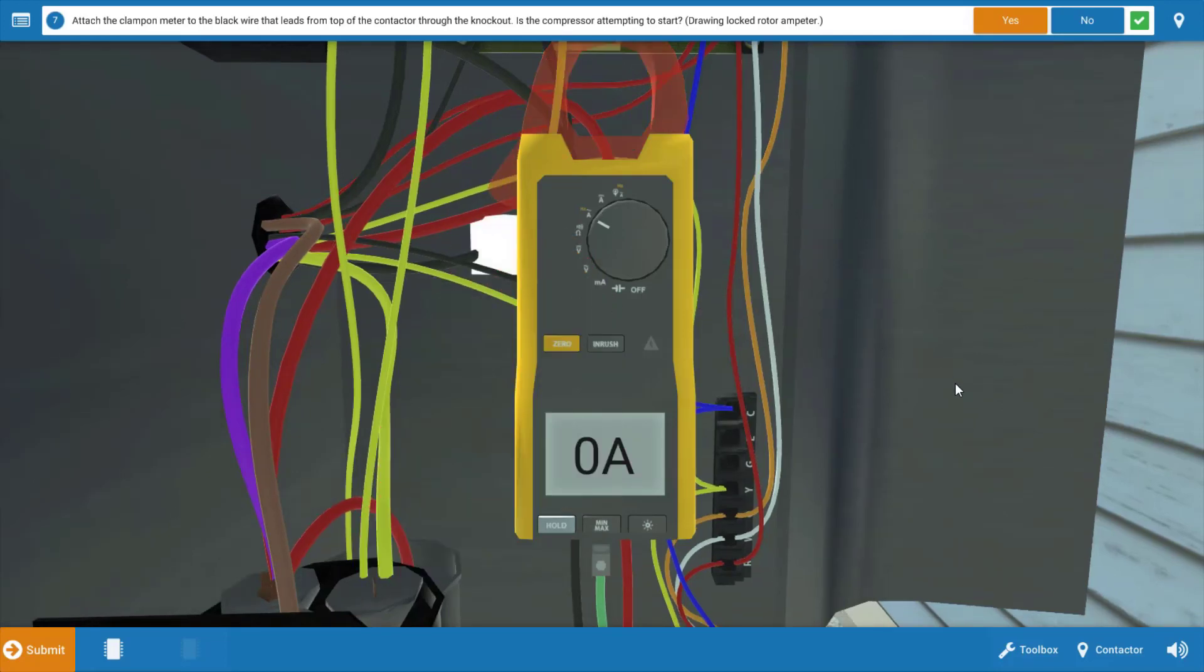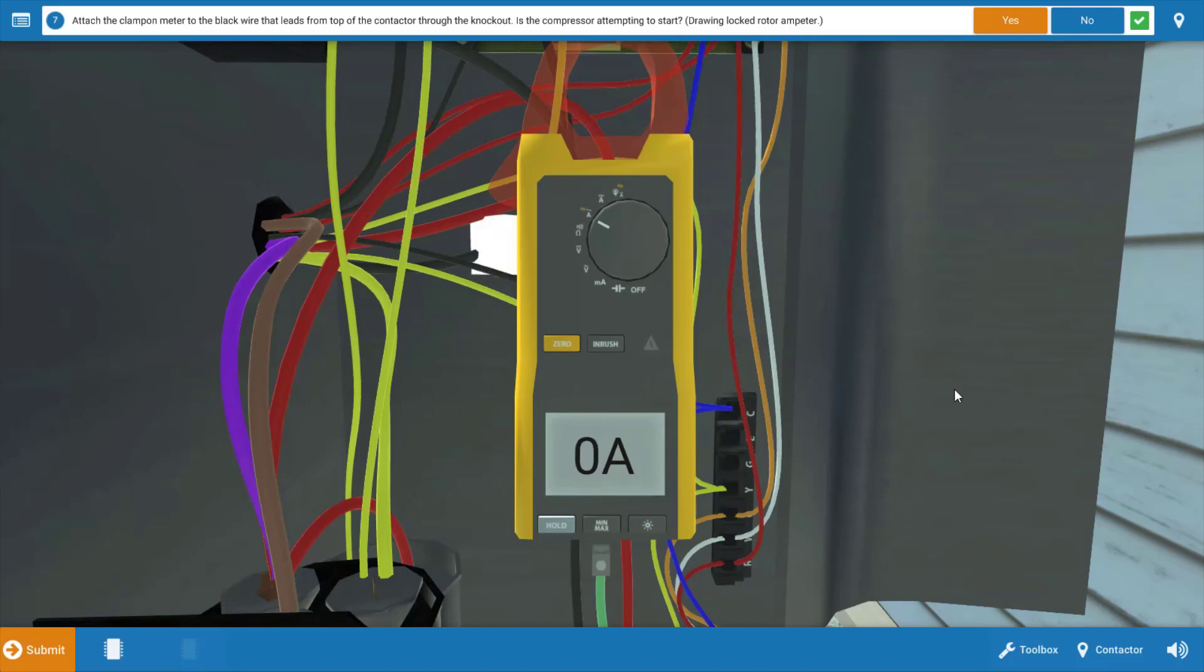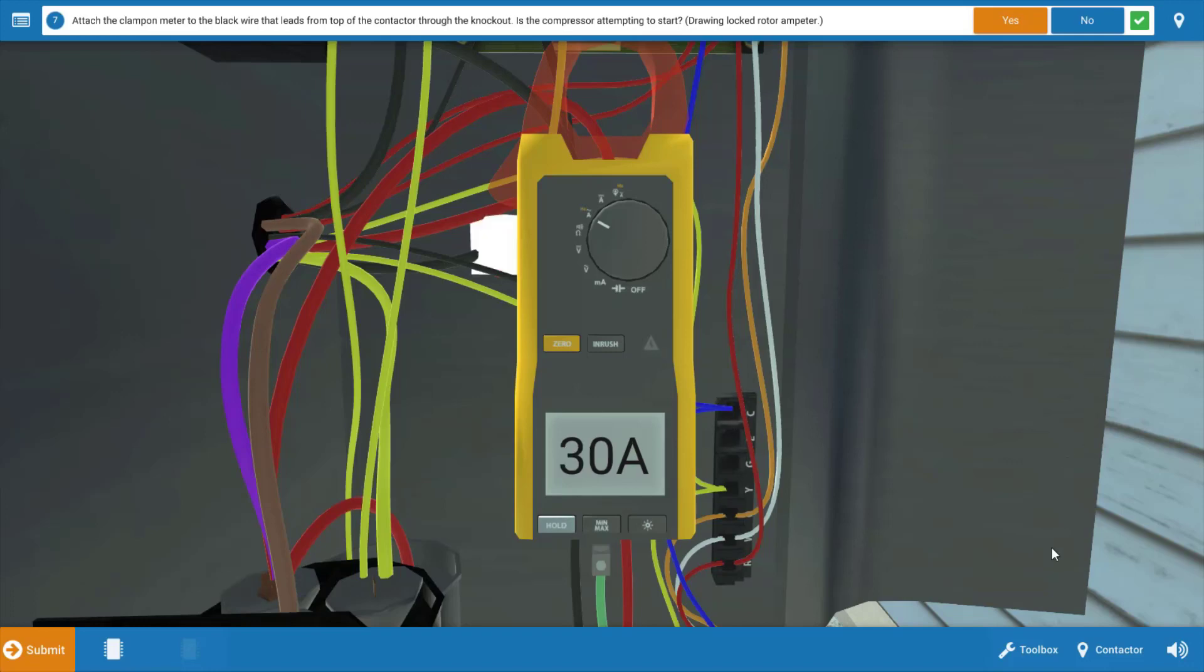And when we do that, we can see that we have zero amps here, but then it goes to 30 amps for just a brief second. This is the locked rotor condition of the compressor. It's attempting to start on one of the windings, but it's not able to turn over. So we need to investigate a few problems here.